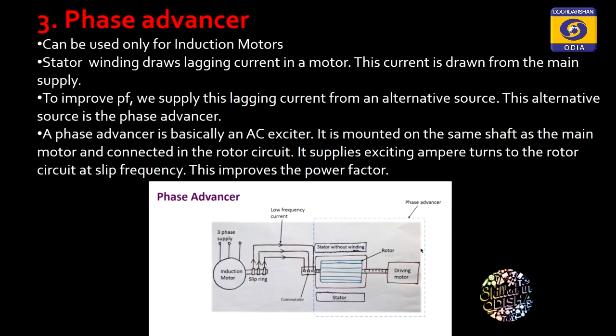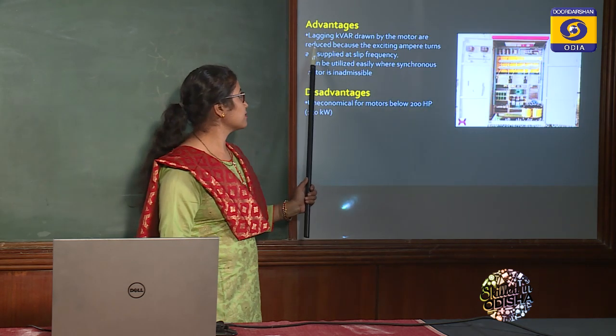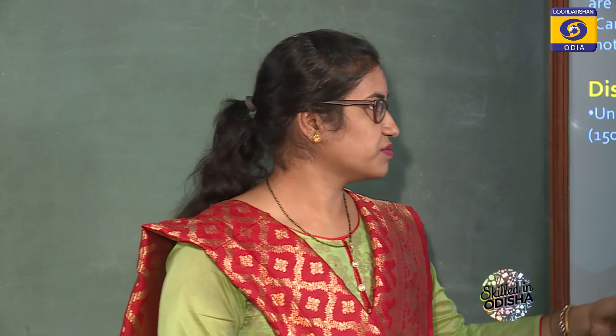The next method is the phase advancer, which is basically used with induction motors. An induction motor draws an exciting lagging current. To provide excitation current from an external source, the phase advancer is coupled to the induction motor on the same shaft. Advantages: the lagging reactive current drawn by the motor is reduced because the exciting ampere-turns are supplied at slip frequency. It is economical for motors rated above 200 horsepower.